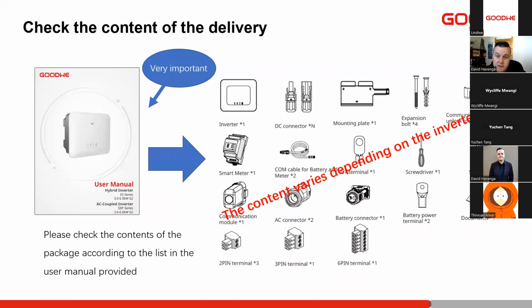It's very important to first consult your manual, check that you have all your components. Very often when we open the box, we might hang the inverter first and all the other components we throw to one side, and then things are lost in the installation. It's very important to check what you have, what you've received in the box, what's in the accessories. So any external connector, any proprietary connector, anything like that, keep it safe, keep it one side, and also install all of them onto the device, because you never know when you might need them in future.